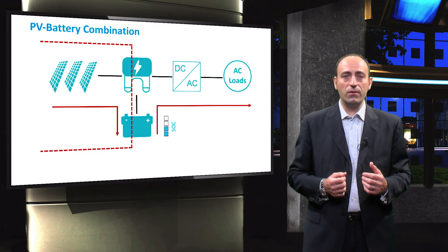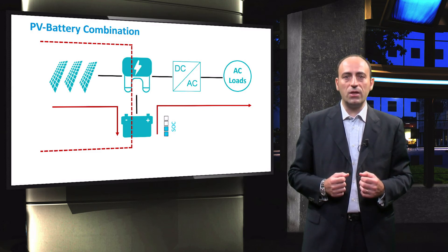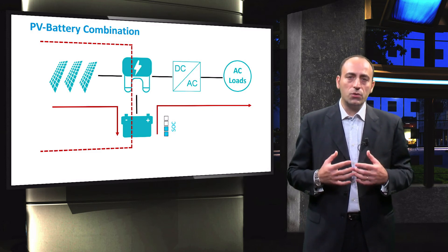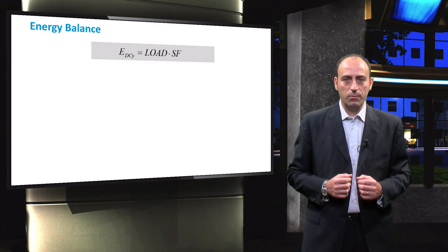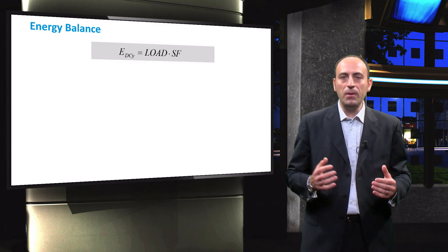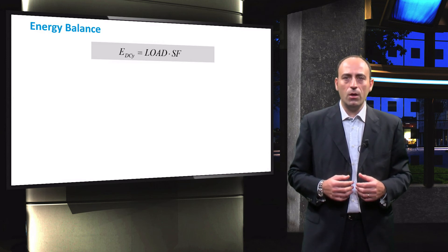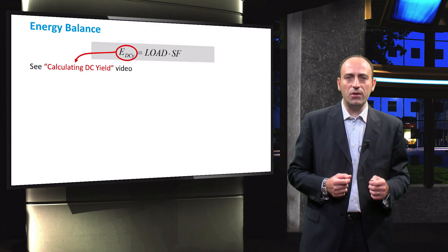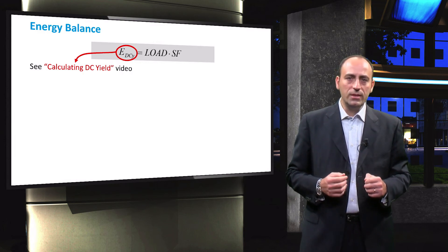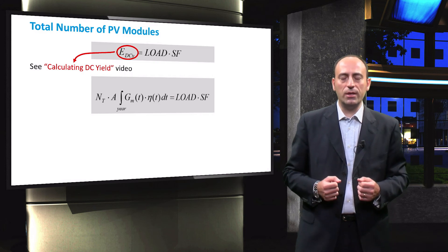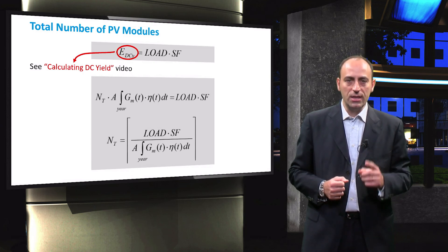After sizing the battery bank and the inverter, it is the turn of the PV array. For that, we focus on the PV-battery bank combination side of the system. In order to size the PV array, the energy balance approach is followed, similarly to the design of the grid-connected PV system. Here, the energy consumed by the loads and the PV generation are balanced over an entire year. Additionally, a sizing factor is also included. The procedure to calculate the DC energy yield from the PV is explained in detail in the video 'Calculating the DC Yield.' From this energy balance, the number of PV modules required can be calculated — it is equal to the product of the load demand and sizing factor divided by the energy generated by a single PV module.